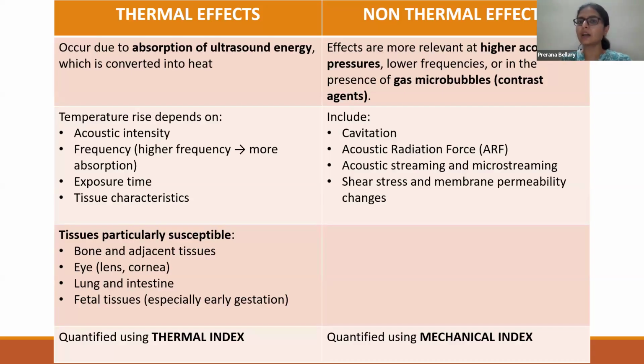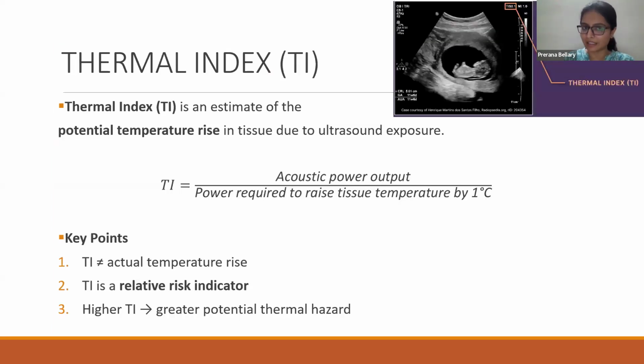The non-thermal effects are more relevant at a higher acoustic pressure, low frequency, or if there is some gas microbubble, especially when we use contrast agents. It includes cavitation, acoustic radiation force, acoustic streaming, microstreaming, shear stress, and membrane permeability changes. And it is quantified using the mechanical index. So both the thermal index and the mechanical index will be displayed on the top right corner of our ultrasound screens. Thermal index is an estimate of the potential temperature rise in the tissue because of ultrasound exposure.